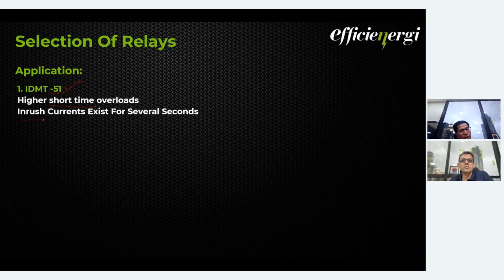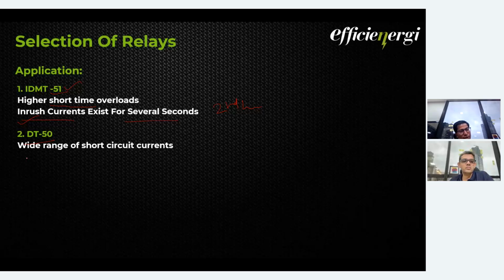The inrush current exists for several seconds. Though we have second harmonics blocking, we can have the 51 installed, maybe extremely inverse or very inverse in nature, which can take care of the inrush currents. Then we have definite time, that is 50. Where there is a wide range of short circuit currents, we normally use 50. And the second case is when no current grading is possible, only time grading. There we use definite time, that is 50.